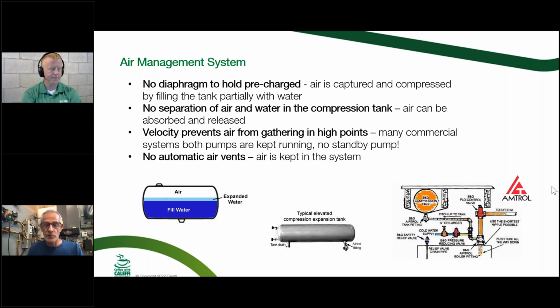In the summer, when the boiler's off, the air that's in that bubble can be reabsorbed into the water. And then if you start venting radiators at the next heating season, you're going to vent away your air bubble. So on the very far right there, a couple of manufacturers make a couple of fittings that make these tanks work or behave a little bit better.